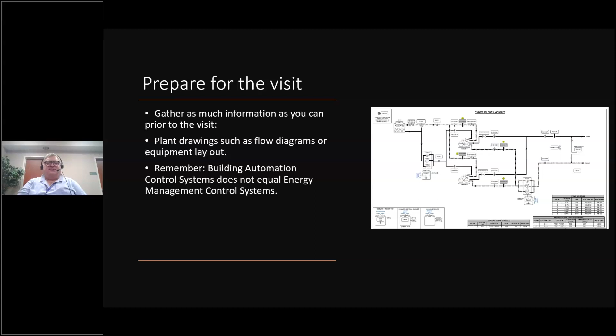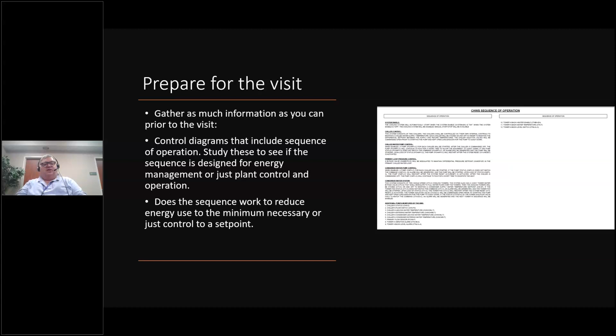Control diagrams that include sequence of operation will tell you whether you're on an energy management project or just a plant control operation. If you see things like 'change the set point to this in response to something else,' then you might be into more energy management, versus 'control the set point to this and fixed' - it doesn't change at all, we're constantly going to keep the temperature the same. Does the sequence work to reduce energy use to the minimum necessary or just control to a set point? That's what divides the line between controls and energy management.